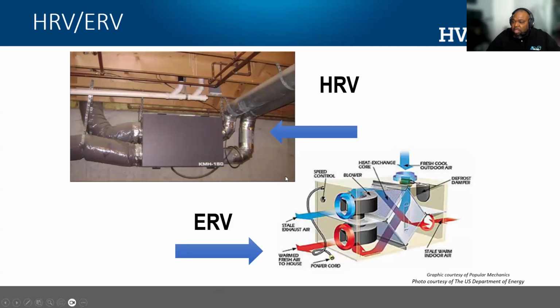What these do, they have two fans here. They're taking air from outside that is unconditioned, unclean, unfiltered, not properly humidified. It's raw air from outside, and as it travels into the ERV or HRV, energy is being given up from the exhausting airstream. So the stale air that you're trying to exhaust has energy that you pay for. It's going to deliver some of that energy into the incoming airstream, so that way you can recover the BTUs that you spent. Again, it's not 100%. There are some losses. However, it's a lot better than completely displacing the air that you have inside your house that you already paid for.